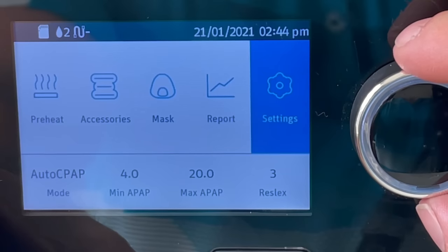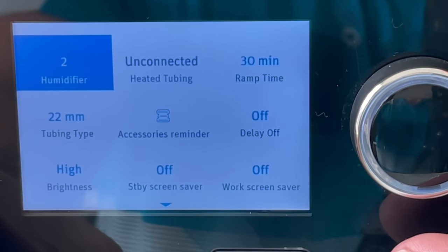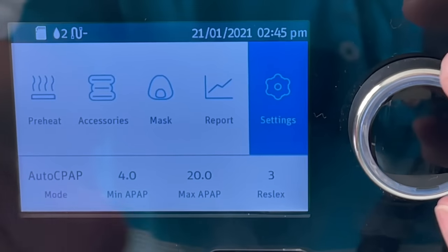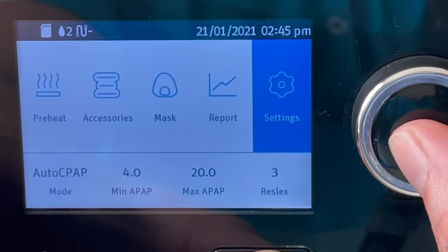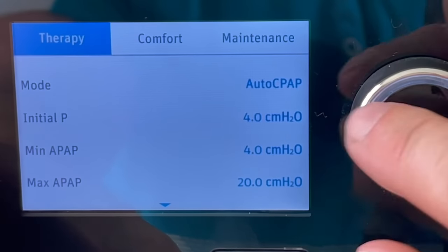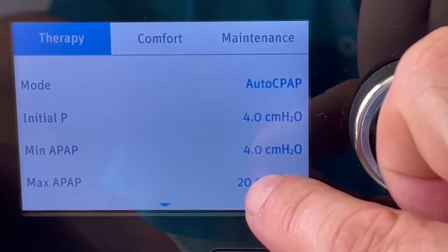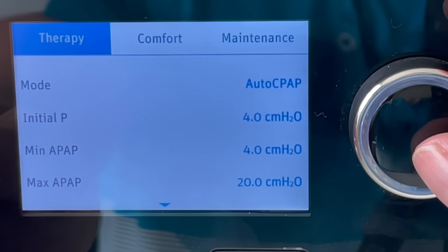So now we're going to go into the settings to change some of our pressure settings to optimise things. If I click this click wheel and go to settings, this is the basic menu — you can see there are no actual pressure settings here. But if I go back out again and hold this button down along with the home button simultaneously, it's going to open up a different menu — that's the clinical menu. Now we have access to all these pressure levels, plus some comfort features and maintenance features. We're looking at therapy today. You can see here: 4 and 20. So this is the minimum level 4, maximum level 20. 4 is as low as this machine will go and 20 is as high as it will go. This has basically just come out of the box and the pressure levels haven't been optimised.